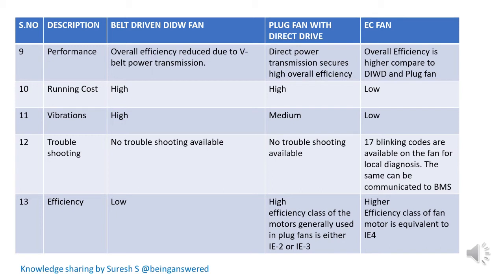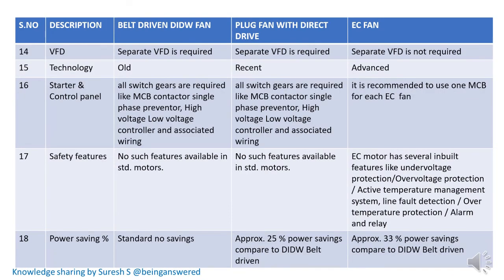For efficiency, belt driven fan will be low, plug fan will be high, and EC fan will be higher. In the plug fan, they use motors of IE2 or IE3, whereas in EC fan the efficiency of the fan motor is equivalent to IE4. For controlling the speed of the motor, a VFD is required as a separate device for plug fan and belt driven DIDW fan, but EC fan will have an inbuilt VFD, so no separate VFD is required.